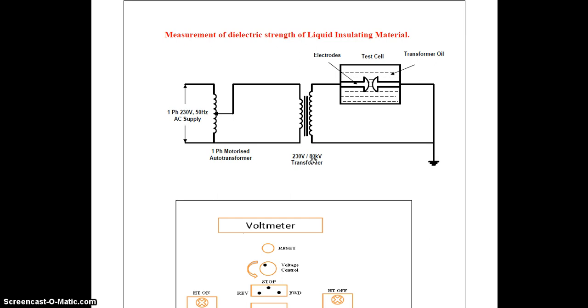Then the secondary side of the transformer is connected to the electrode test cell. One electrode is connected to the secondary winding and the other is connected to the ground. In the test cell, transformer oil is filled, and then we obtain the dielectric strength of the liquid insulating material.